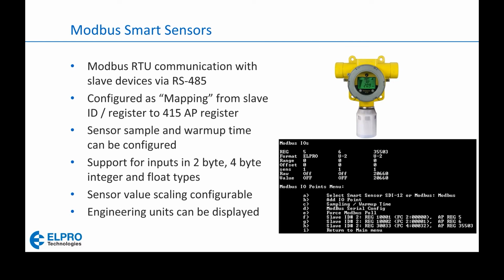Okay. Now we have Modbus smart sensors out there. These are just pressure transmitters, level transmitters that have a 4 to 20 milliamp output, and a Modbus output via RS-485, usually in addition to the 4 to 20. But you can get a lot more diagnostic data via Modbus, so it's becoming quite popular these days. You can pull span, zero, calibration settings, that sort of thing out of these devices now. So Modbus gives you quite a range of diagnostics here.